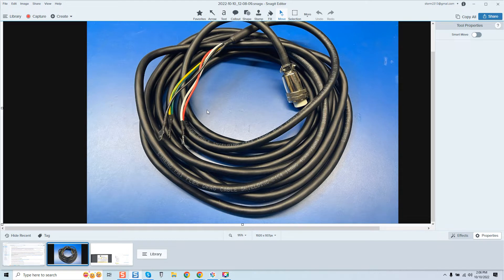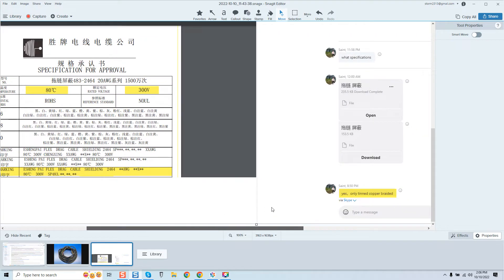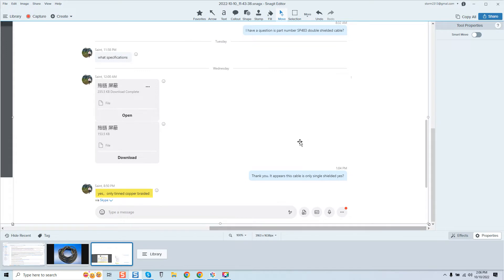Proceed with extreme caution. I want to point your eyes again to part number SP483 — 20-gauge, 80 degrees Celsius, 300-volt. I went and contacted the vendor. I asked: 'Is part number SP483 a double-shielded cable?' He gave me the specs. I asked again and he confirmed: it is only single-shielded — only tin copper braided.